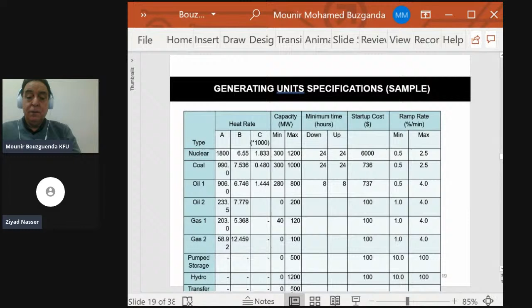For pump storage, we only accept 500 megawatt, and for hydro, maximum is 1200. It exists, as a matter of fact. Such a hydro availability of 1200 megawatt exists in the system. This is the study scenario.